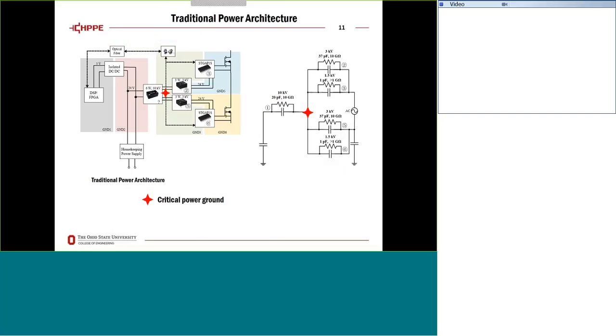So with that, if we look at the traditional power stage, everything comes from the housekeeping power supply. It not only provides power to the gate drive, but also the DSP, FPGA, everything in the control. But we do need to have isolation between the control stage and the power stage. So that's the reason we have a 10 kV isolation DC-DC converter at a low voltage input, low voltage output, low power, 6 watt.